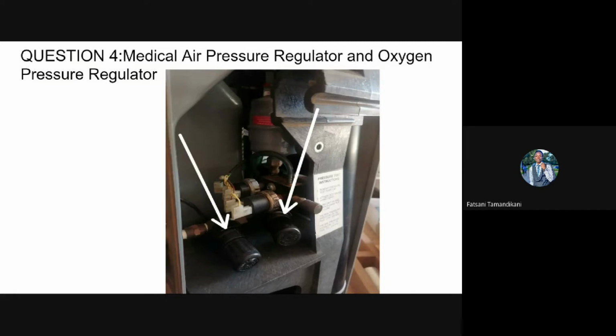And the second pressure regulator is attached to the product tank of the concentrator, and it is the oxygen pressure regulator. And this is the one that you have to adjust. Now, to adjust the regulator, you have to pull the adjusting knob of the pressure regulator and turn it anti-clockwise to reduce the pressure, or clockwise to increase the pressure. In order to adjust pressure for the 5-liter models of the AirSep, you open the flow meter all the way up to the maximum and then adjust the pressure regulator till the flow meter bobbin settles on the 5-liter per minute mark on the flow meter.